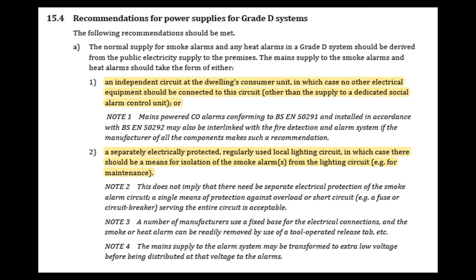Or a separately electrically protected, regularly used local lighting circuit, in which case there should be means for isolation of the smoke alarms from the lighting circuit, i.e. for maintenance. So what we're saying here is we can come off the local lighting. It doesn't mean that if you've got a two-storey building, all the smokes can come off the downstairs lighting. It means that you come off the local lighting to that floor or to that area, should I say. And there are some pros and cons about it. I'll try and outline this, right? So I personally think it is better to install off local lighting and use radio bases.